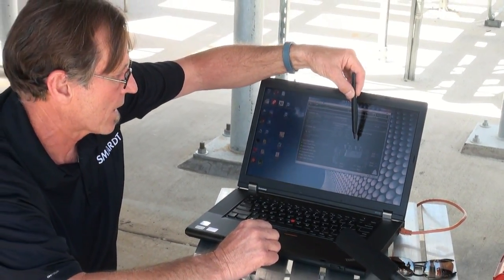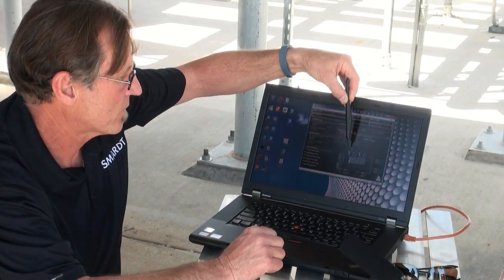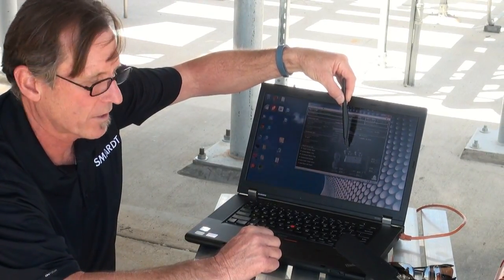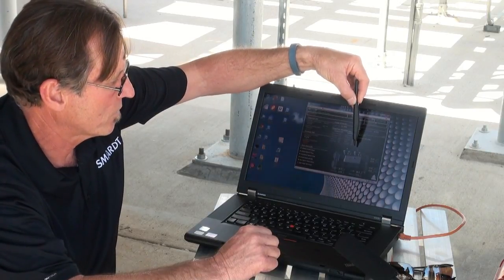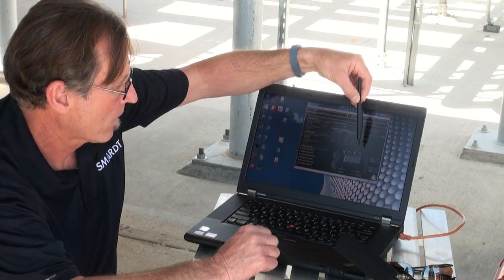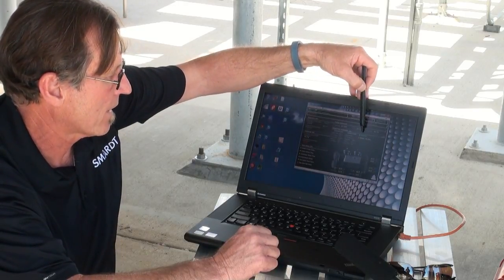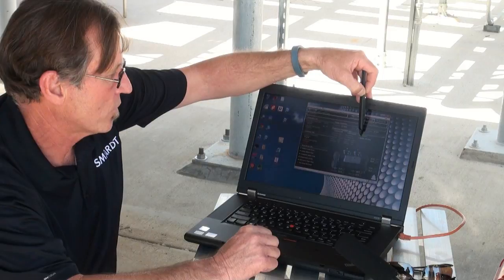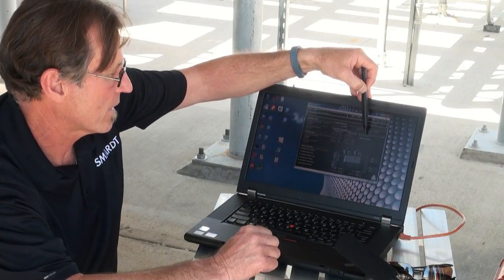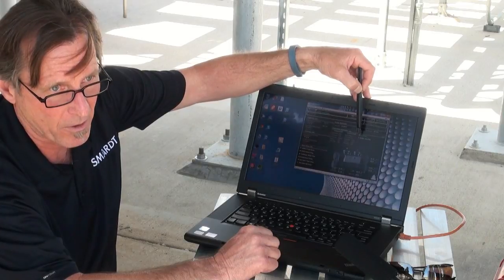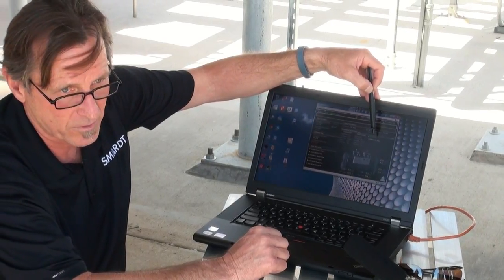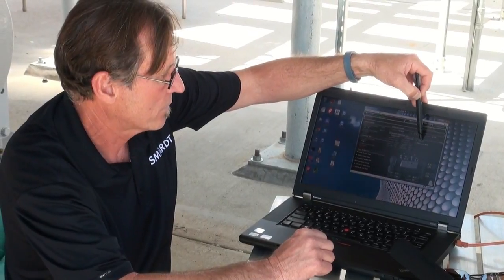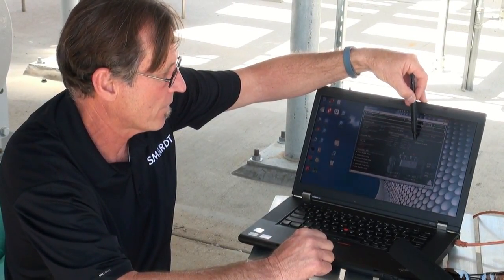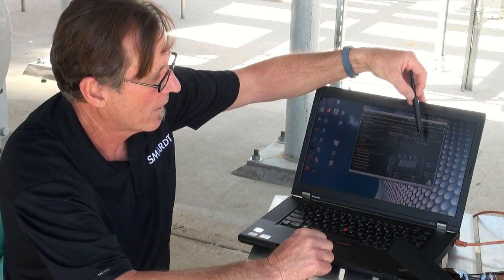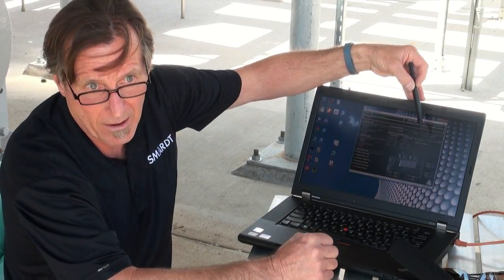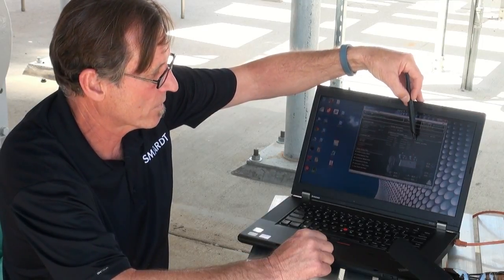Right now we've got a couple of LEDs on each compressor. One's green, one's red. Of course the green one is compressor 1, which is running. Number 2 is offline at the moment, so it's red. Up here it tells us that 1 is running and 2 is ready to run. That's important. If the compressor was powered off, it would say offline. So it's ready to run, all systems are go. If there's a problem, it'll indicate it here, maybe that it's locked out, and it'll show what the problem is, why that compressor is not running.